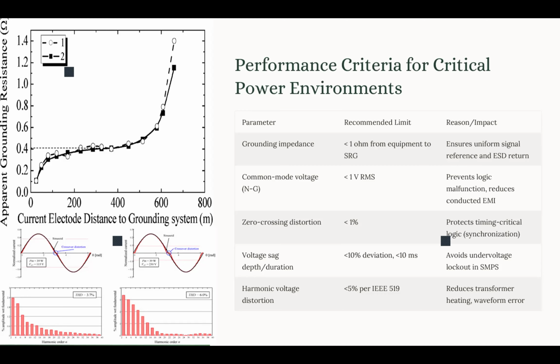Now that drop of voltage, that sag in the waveform, would not be instantaneous, like in a fraction of a nanosecond or millisecond. There is a duration for which that voltage sag continues to exist. That duration is the voltage sag duration. Now we have limits recommended by IEEE 1100. The voltage sag depth should not be more than 10% of nominal voltage. So maximum voltage sag deviation should be 10% of our nominal voltage. And also we should not have a voltage sag longer than 10 milliseconds. So the duration of the voltage sag is bounded by the limit of 10 milliseconds.